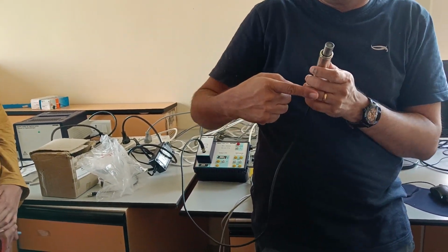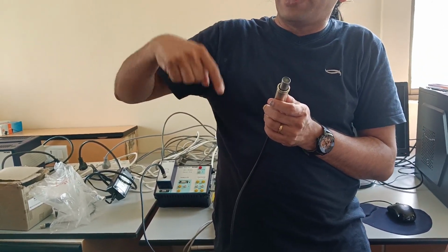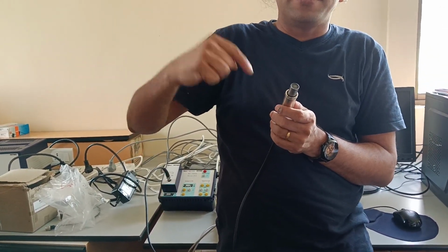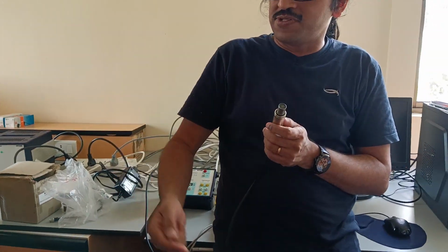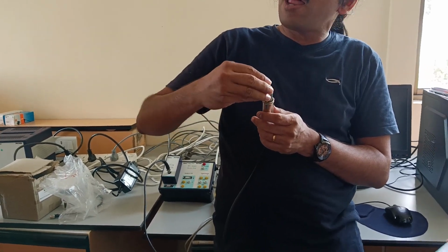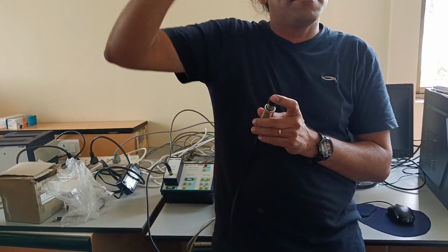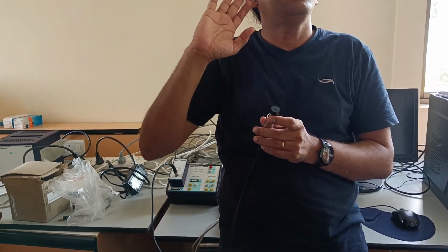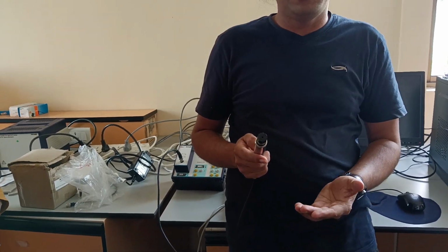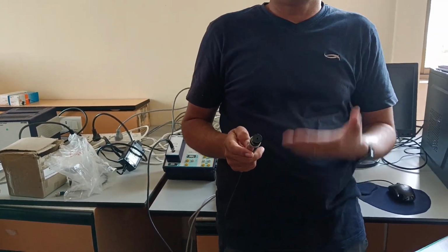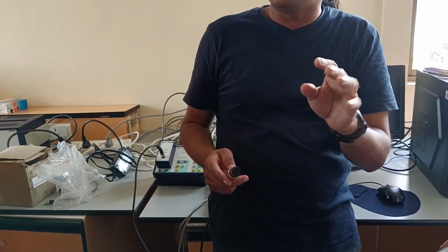As they rush, their energy increases very rapidly, and then they collide with other atoms and ionize them, producing more electrons. They also get accelerated and hit other atoms, and in the process produce a large number of charged particles, and you get a very rapid pulse. It just tells you that something hit the detector. That's all. It doesn't tell you how much the energy is, whether it is an alpha particle, gamma, or what it is. It just says high energy radiation hit you.